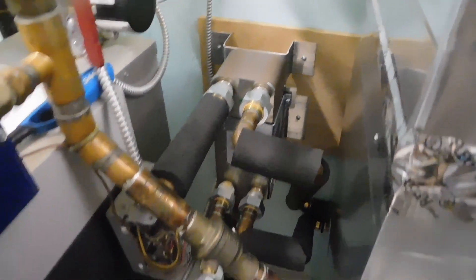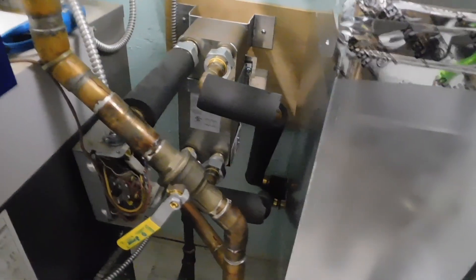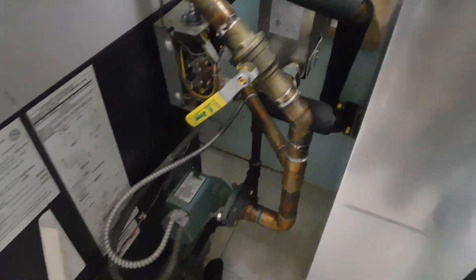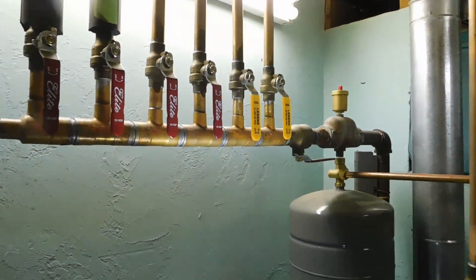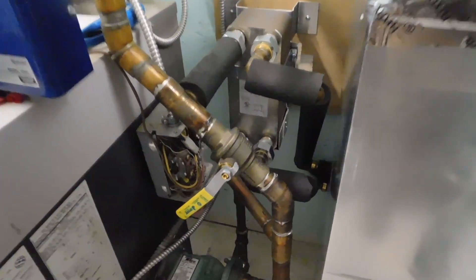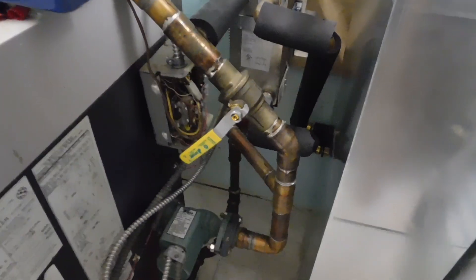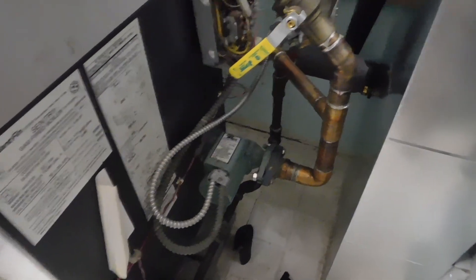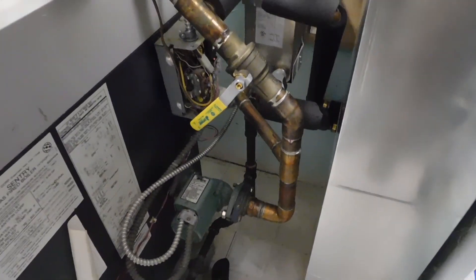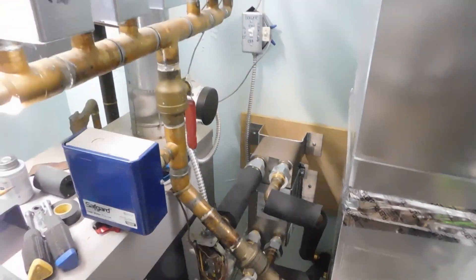And you'll have to get with the pros—I talked to at least two different sales companies and a local company about the size of the plate exchanger I needed for my house, and I settled on a 40-plate exchanger. Obviously, everybody's plumbing is a little bit different for their actual boiler setups, but this worked great all winter long. Not a single issue. That one single Taco pump was able to supply the whole house when needed. And yeah, it was fantastic.